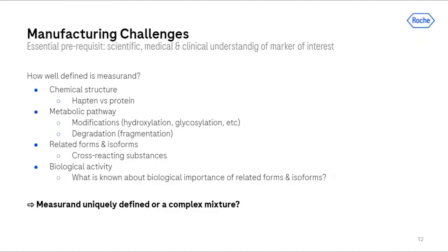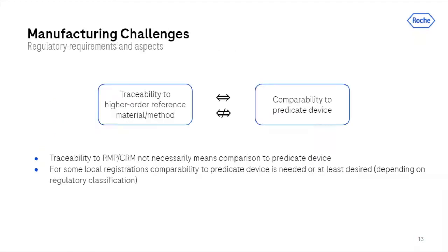In a nutshell, one has to get a clear picture and definition of the measurand — only this understanding allows setting up traceability and specificity of an assay. Without any doubt, traceability to a higher-order reference material or method has to be the goal of an IVD development. However, registration in some countries requires or would at least benefit from comparability to a comparable IVD predicate device. The traceability of the own IVD product might or might not allow comparability to the competitor product, depending on its calibration hierarchy. Once comparability becomes clear, the registration strategy may be discussed with the respective regulatory bodies.